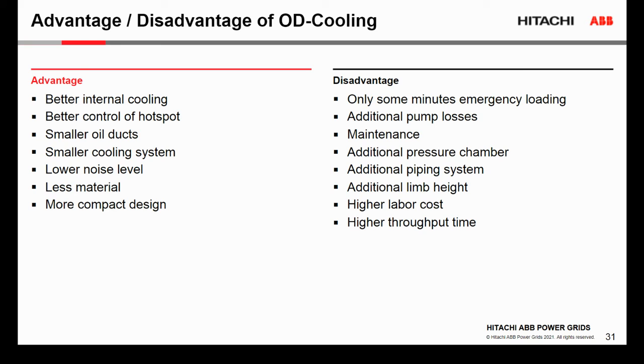The disadvantage is that the transformer must have cooling on when it's energized. Only the solution with radiators will allow us to load the transformer without fans or pumps running. But most of the time, when we have oil-to-air coolers or water coolers, the cooling system must be on all the time when the transformer is energized. With the pumps, we have additional losses. We also increase maintenance. We have to design the pressure chamber. We have to design the piping inside of the transformer, so it changes the design. And with those additional parts, we increase the labor, and this can also increase the production time of the transformer.